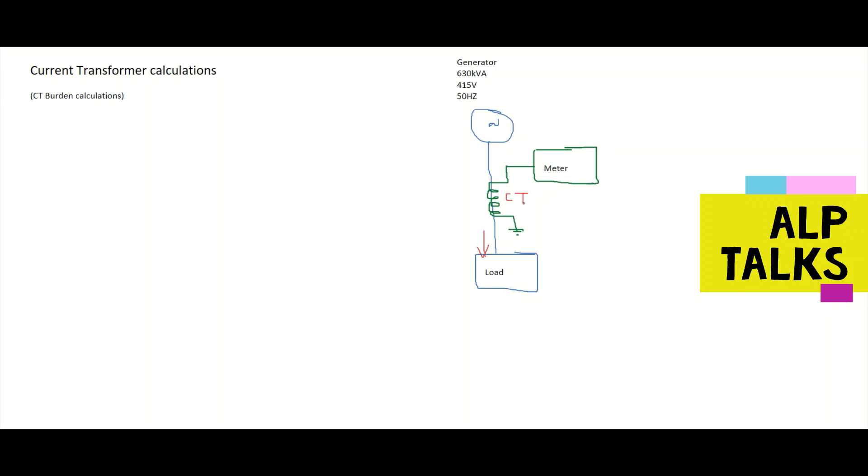So this is the CT, current transformer here. The metering CT, the burden for this CT is 0.2 VA. Similarly, the length of this wire cable, whatever cable is there, the length of that cable is 10 meters. The size of that cable is 2.5 square mm.